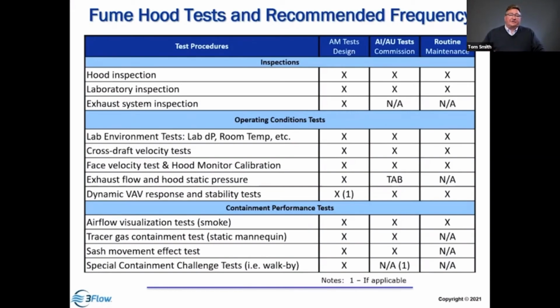So you can look at these tests in terms of how they're applied. From the as-manufactured tests, we want to do all of them plus. We want to do the inspections, the operational tests, and we want to challenge it not only under the static tests with a fixed sash, but also under special tests and dynamic conditions. What are the weaknesses of the hood and where is it going to fail? That's the as-manufactured test.